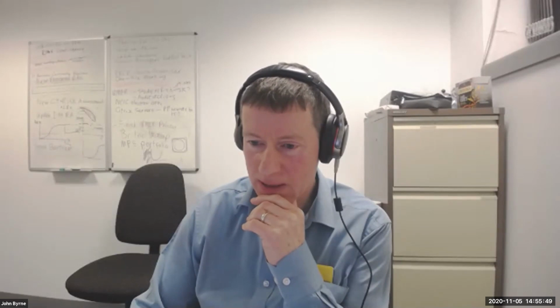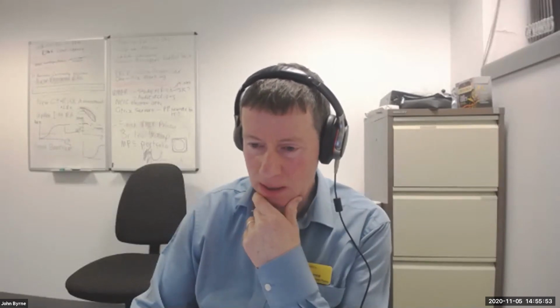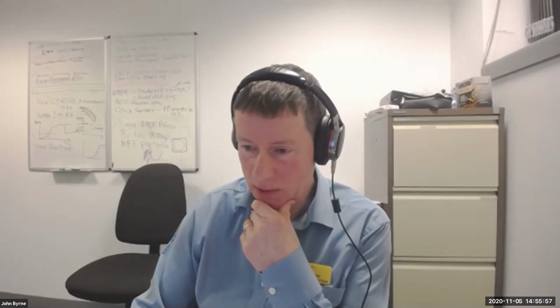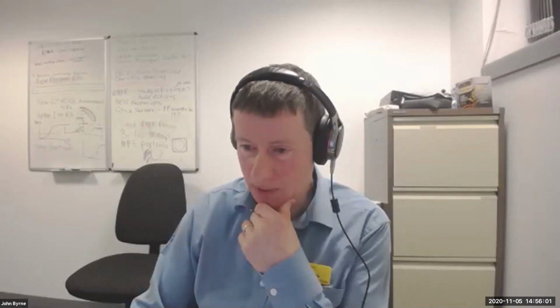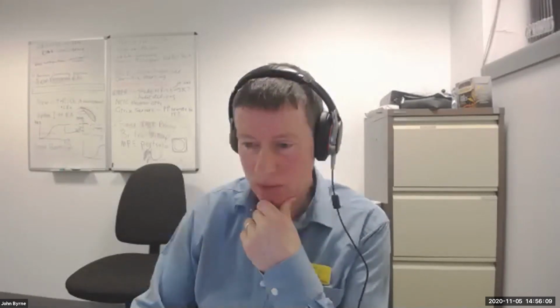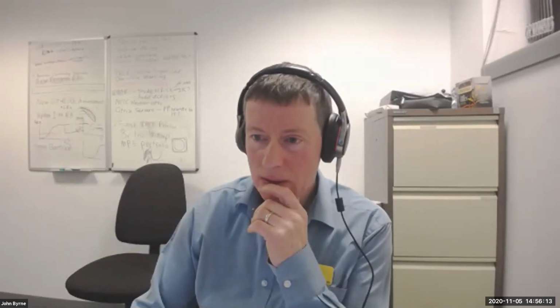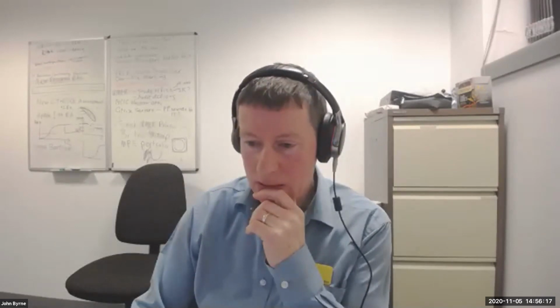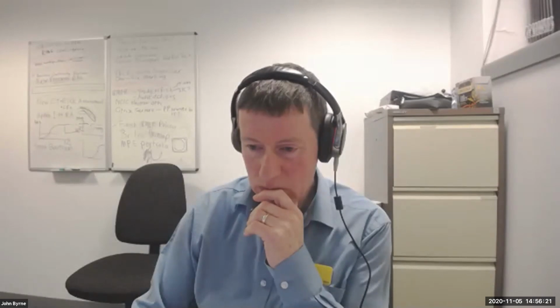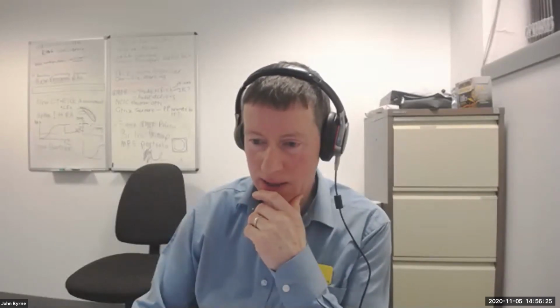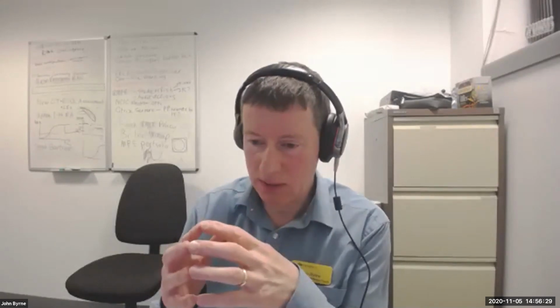Paul Evans has got a good question there. We have 3 questions in the Zoom chat rather than the Q&A. Regarding the chamber-specific quality correction factors tabulated in TRS 483 and measuring dose in small fields, these are tabulated only for a range of detectors, not all, and only at 10 centimeters deep. How would you adapt these factors for other depths? Also, what values would you recommend for measuring intensity modulated fields? Somebody want to respond to that? I think the general answer is, if you do not have the correction factors tabulated, then you have to measure them. And if you measure them, it would be good if you could publish them.